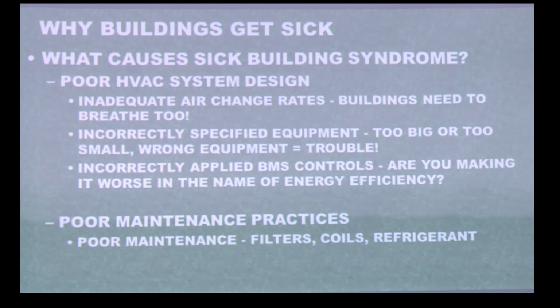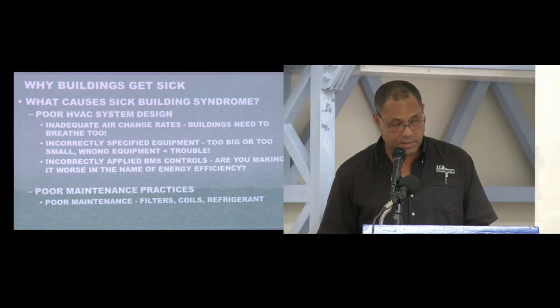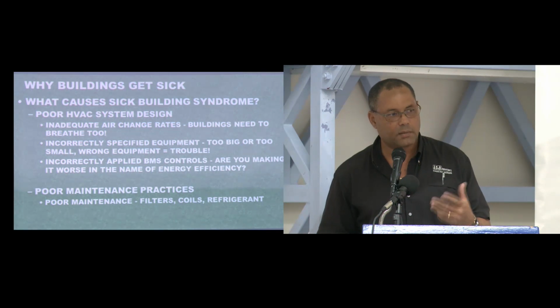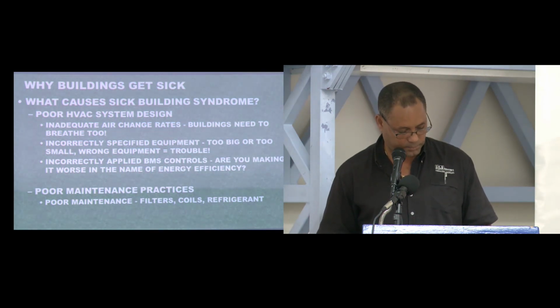Poor maintenance practices. We've seen this one before. Your filters are the first line of defense against dust and other contaminants in the air. If you don't change them regularly, obviously you're risking not only dust getting through or low airflow because they get clogged up, but they can also introduce their own pathogens because they become harbors for mold and mold growth, etc. And that gets into the airstream. Your coils, if they get full of sludge and dirty, they don't transfer heat as well. It means you're not dehumidifying your space, and you end up with high humidity, another perfect scenario for mold growth. A low refrigerant charge can do the same thing. If it's not cooling properly, you don't feel good, and the humidity levels stay high.